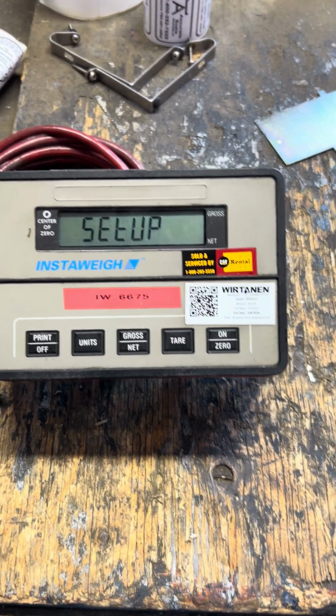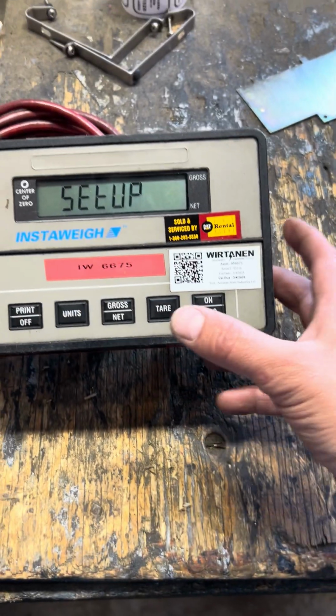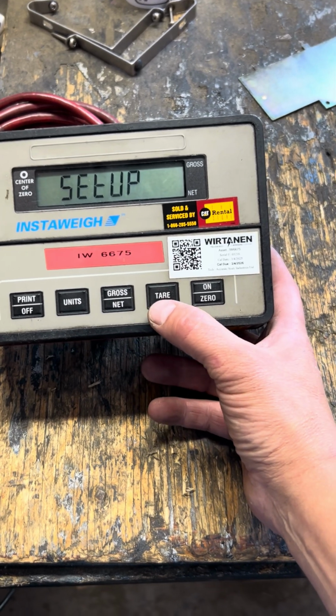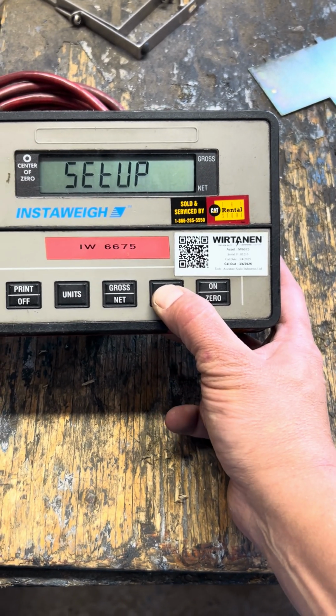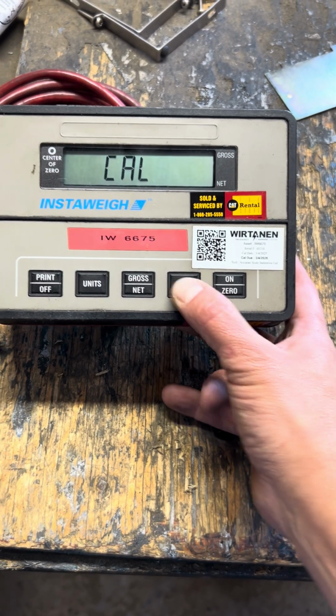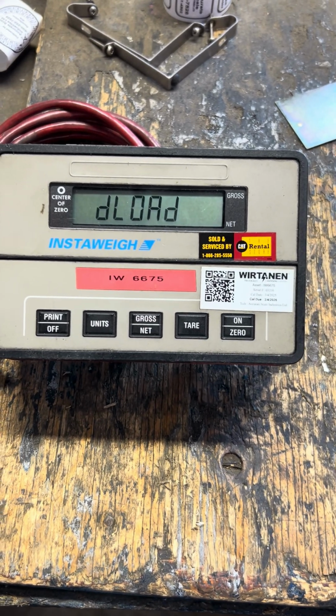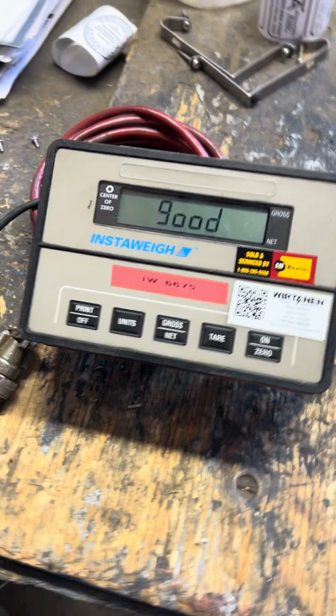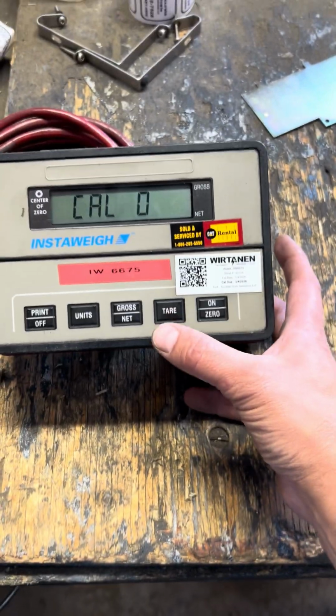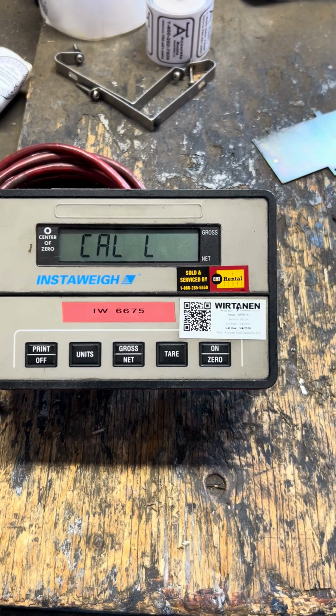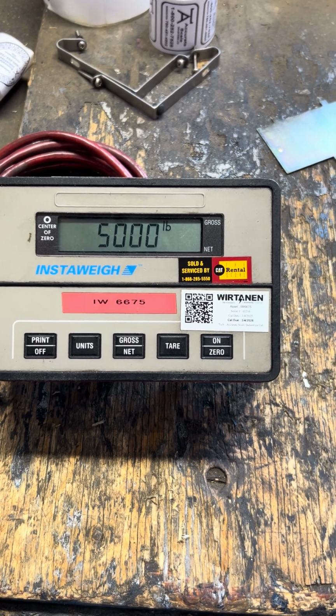So now we have setup. To go to the calibration we press and hold Tare again. Now we have dead load, it's calibrating 0. I have nothing on the scales, it's 0. I press the Tare button again, and now it's asking about 5,000 pounds.